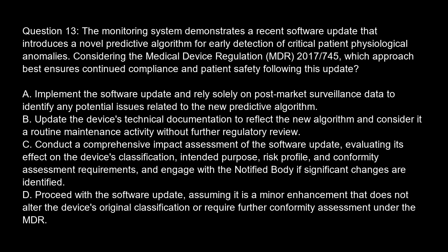Update the device's technical documentation to reflect the new algorithm and consider it a routine maintenance activity without further regulatory review. Option C. Conduct a comprehensive impact assessment of the software update, evaluating its effect on the device's classification, intended purpose, risk profile, and conformity assessment requirements, and engage with the notified body if significant changes are identified. Option D. Proceed with the software update, assuming it is a minor enhancement that does not alter the device's original classification or require further conformity assessment under the MDR.